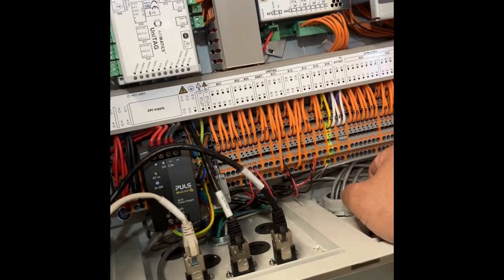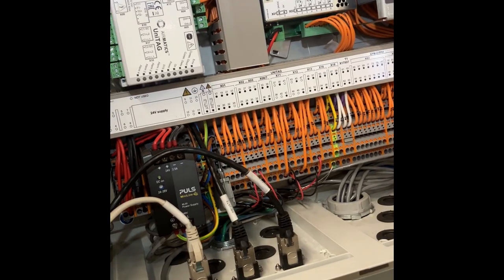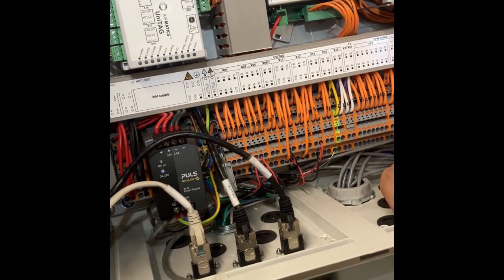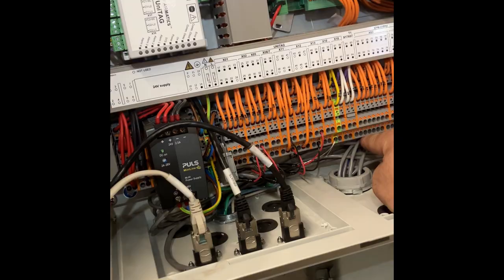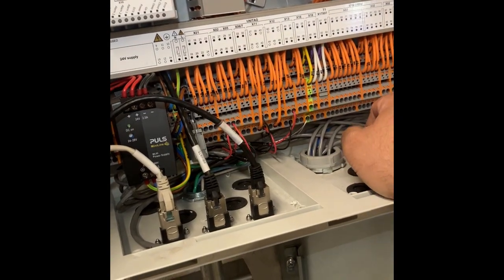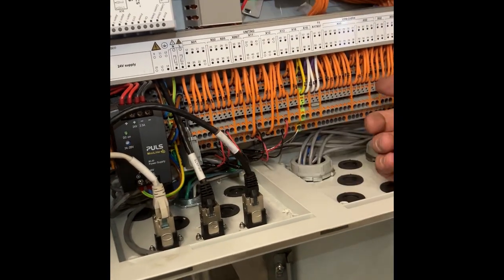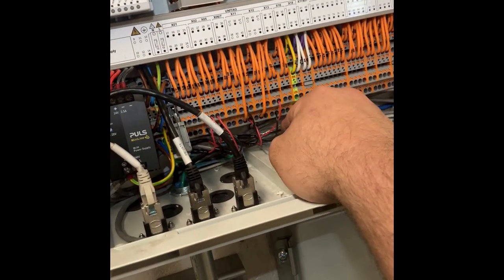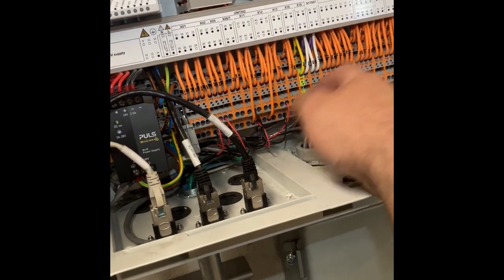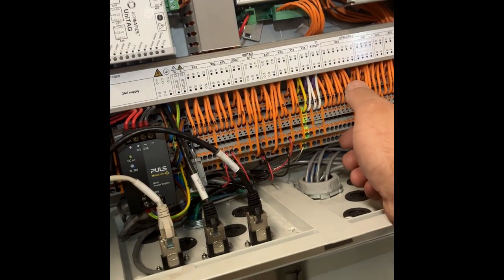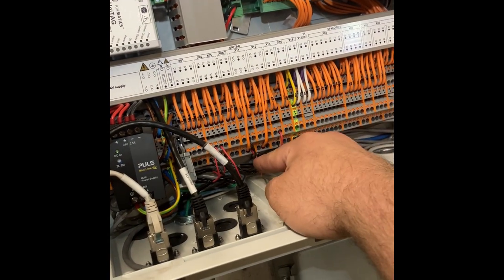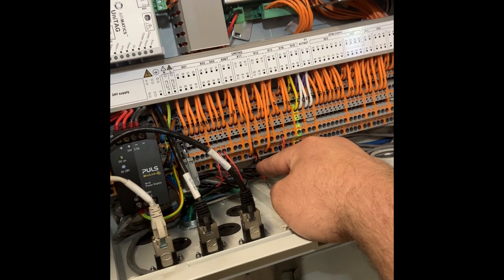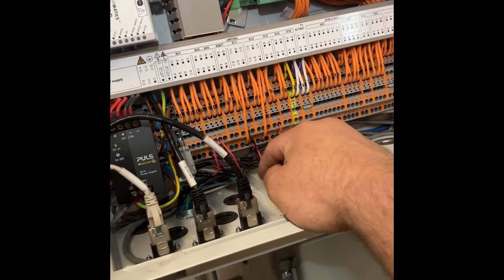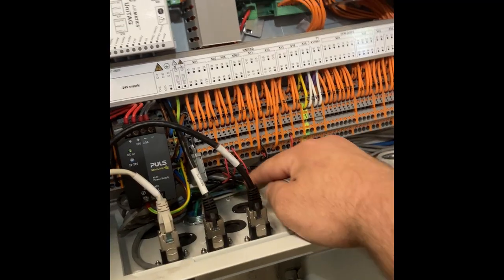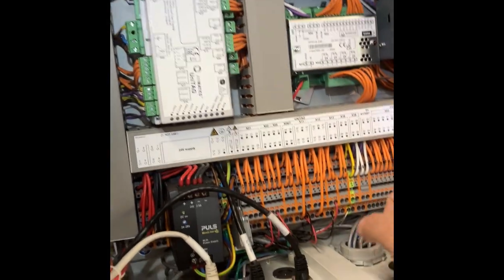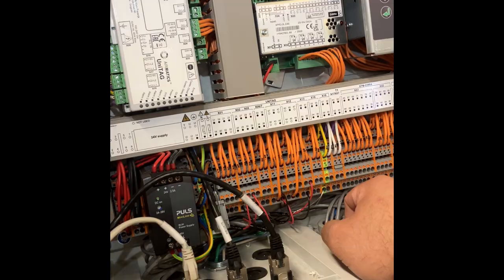And that's it, man. I would call this a pretty basic installation. The only thing we really did kind of outside of the norm is put the dryer fault contacts in. If it wasn't for that, and the dew point monitor which is optional, you'd really just need the sensor wire for air pressure here, 120 coming in to feed the thing, and an Ethernet cable. It is very simple.